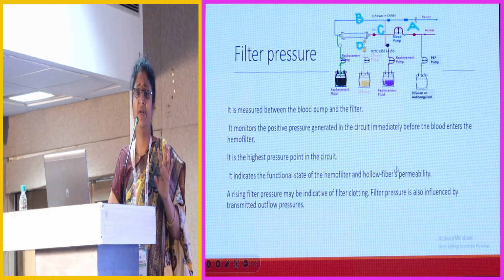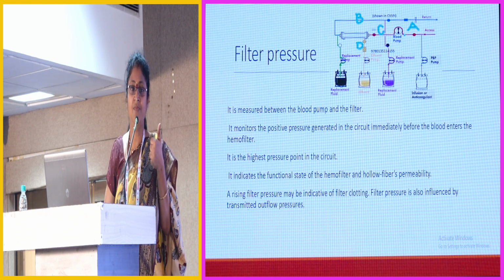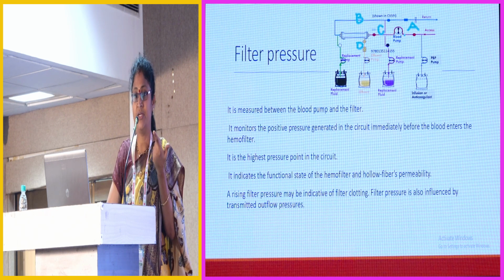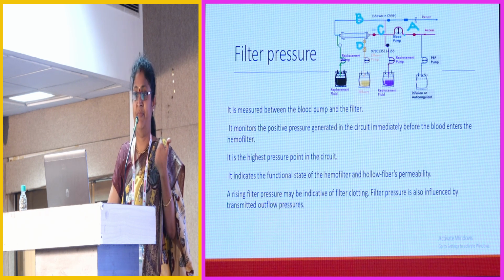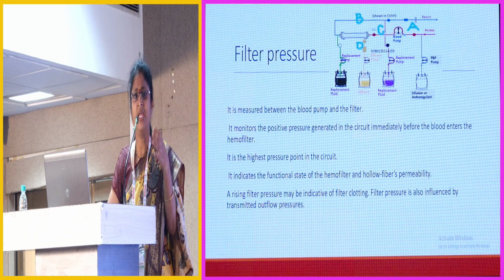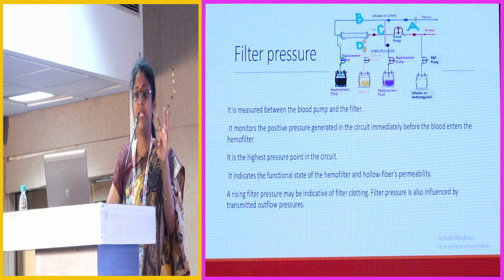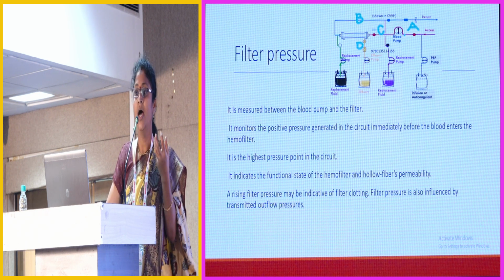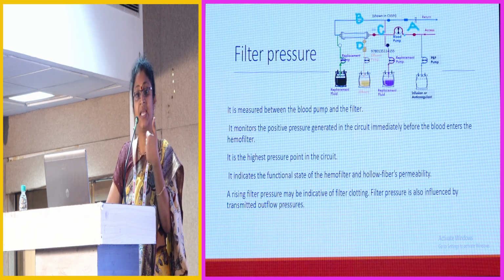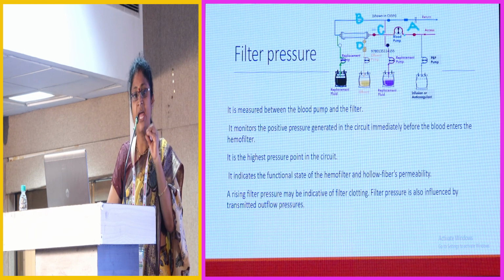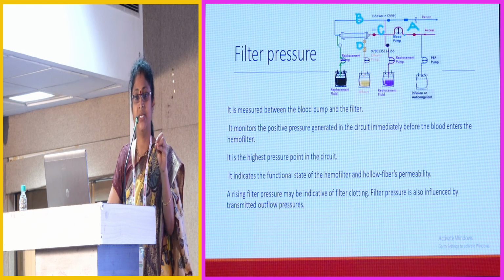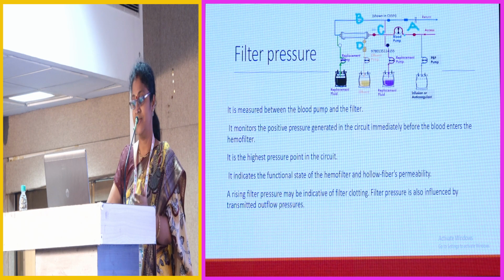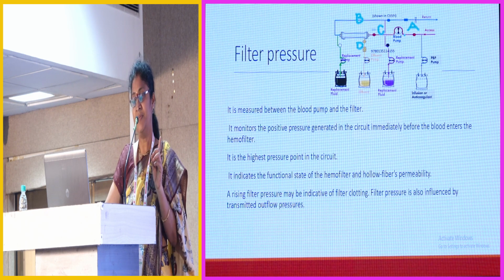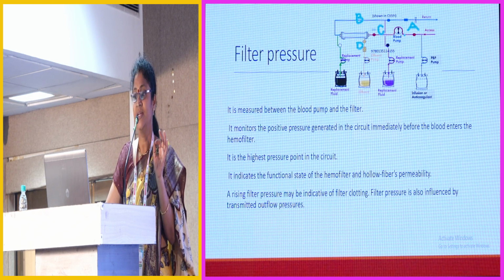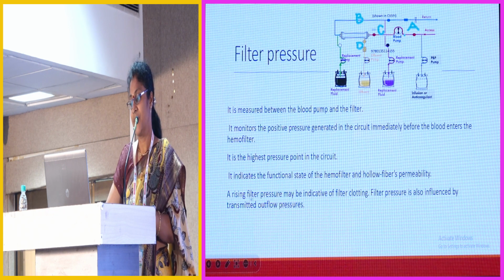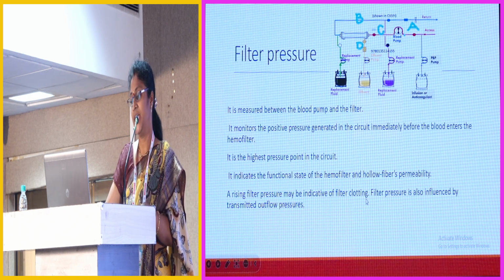So this is very important. You can forget all the pressures, but there are two pressures that you want to remember out of my talk. One is the filter pressure, the other is the TMP. Suppose your filter pressure is going very high, that means the filter is having trouble taking the fluid. How can the trouble come? In the morning we saw that it can come from fouling, the gradual deposition of proteins, red blood cells and all the debris. You get an increase in the filter pressure. So, important to remember, filter pressure represents the filter's life. A rising filter pressure is indicative of filter clotting.